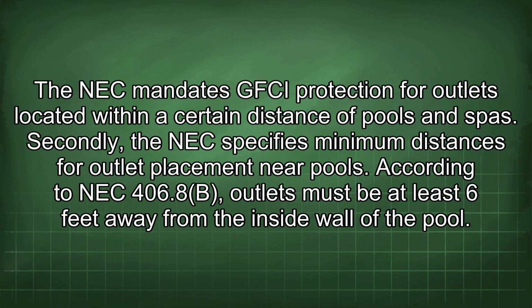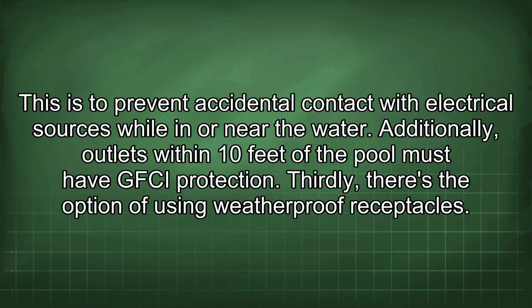Secondly, the NEC specifies minimum distances for outlet placement near pools. According to NEC 406.8b, outlets must be at least 6 feet away from the inside wall of the pool. This is to prevent accidental contact with electrical sources while in or near the water. Additionally, outlets within 10 feet of the pool must have GFCI protection.